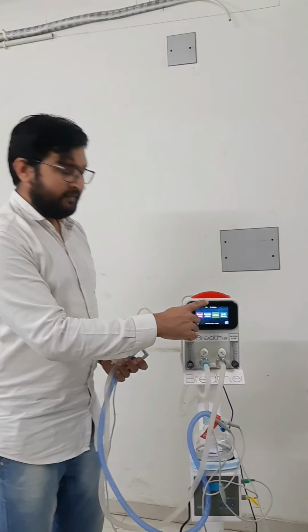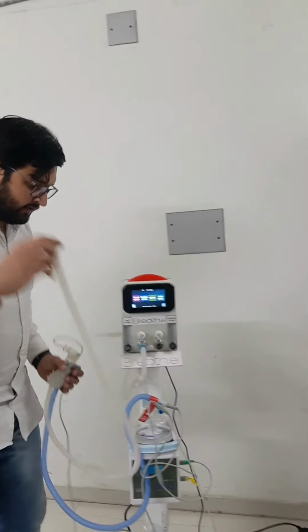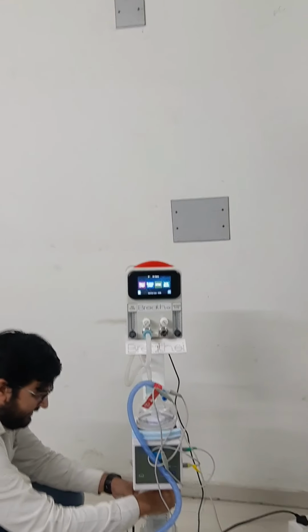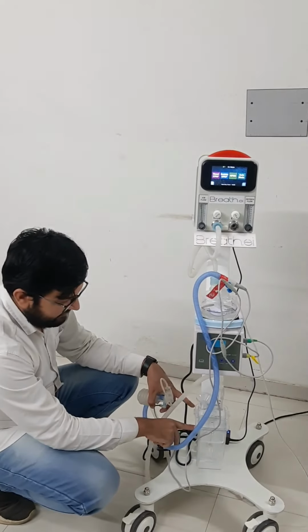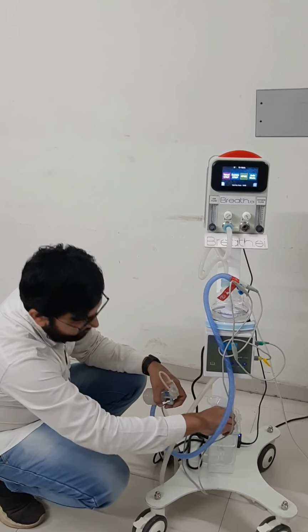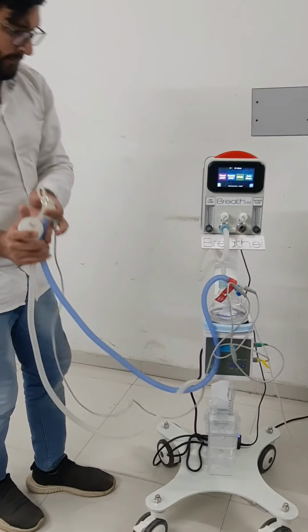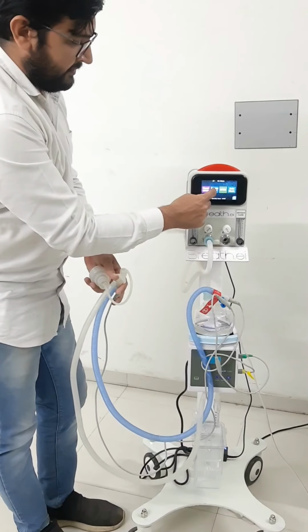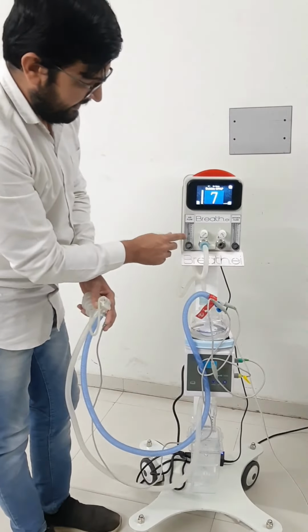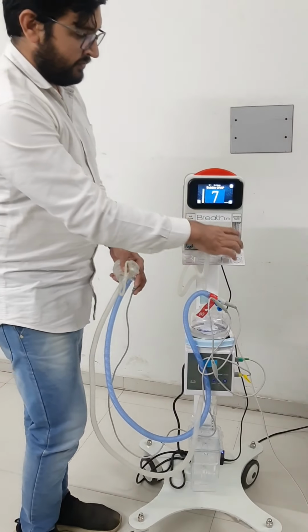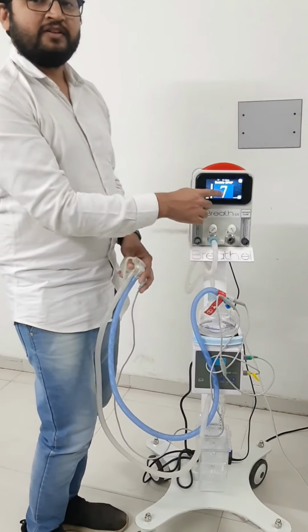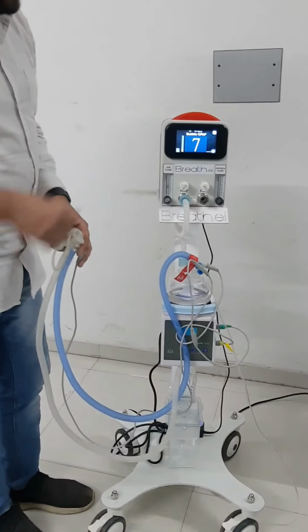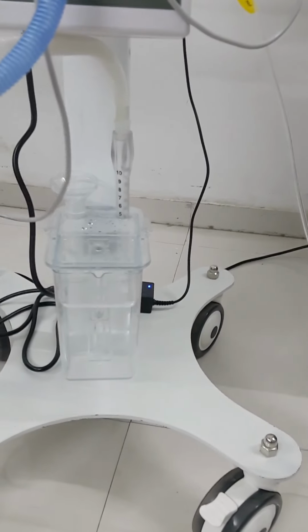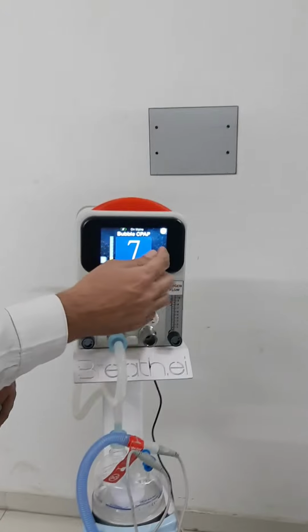The second mode is bubble CPAP. For bubble CPAP, you have to connect the expiratory limb to the bubble CPAP generator. This one. You have to put in the water as per the bubble generator and set the required flow from here. Now for bubble CPAP, just start the bubble CPAP. As earlier, you have to set the flow from here, air and oxygen flow from these two flow meters, and the required flow will be delivered. Again the real time pressure is showing on the screen. Again to stop, just click on the stop button and confirm.